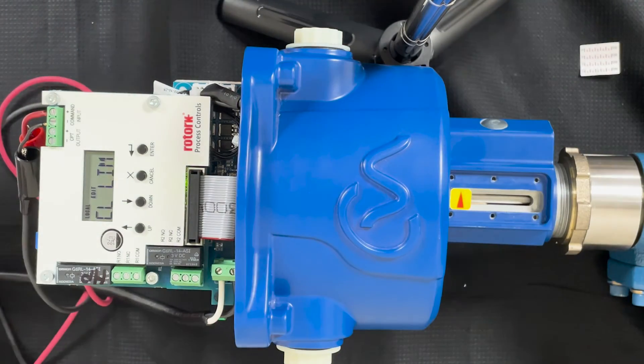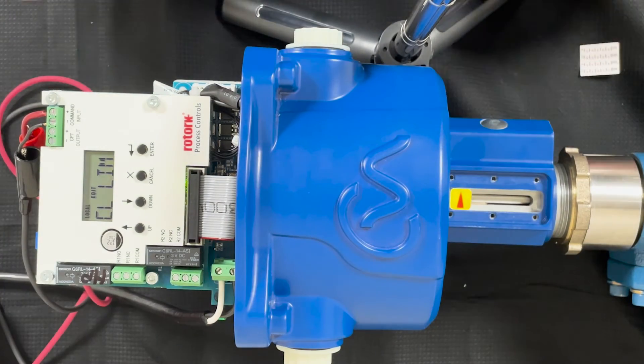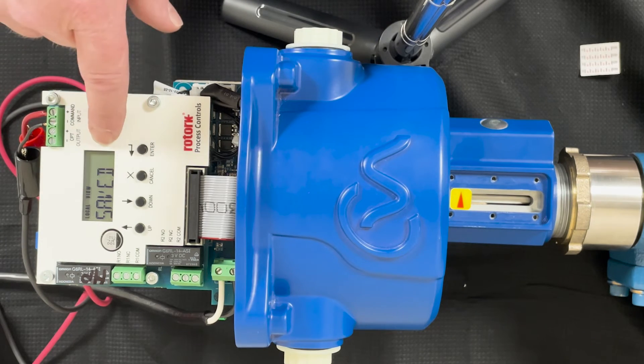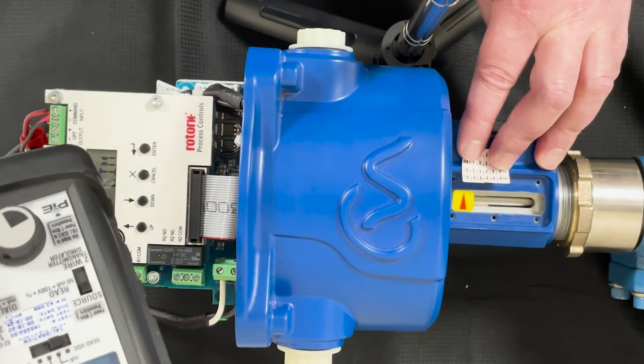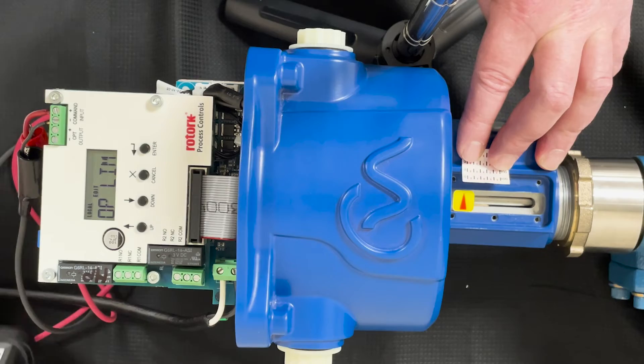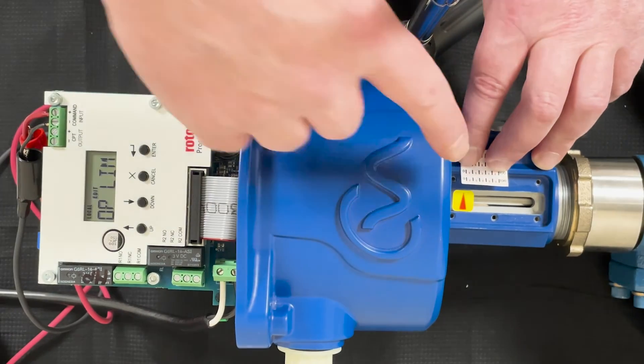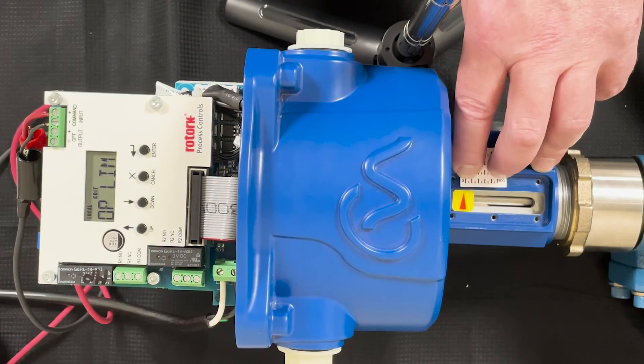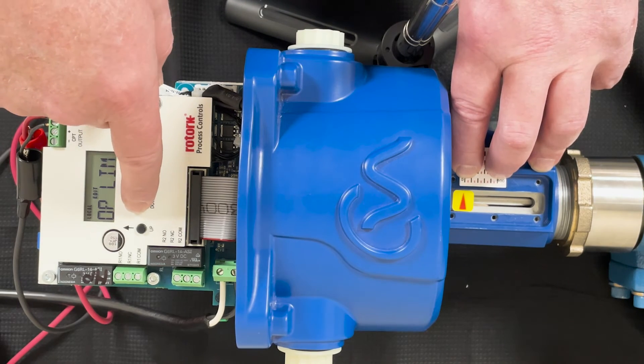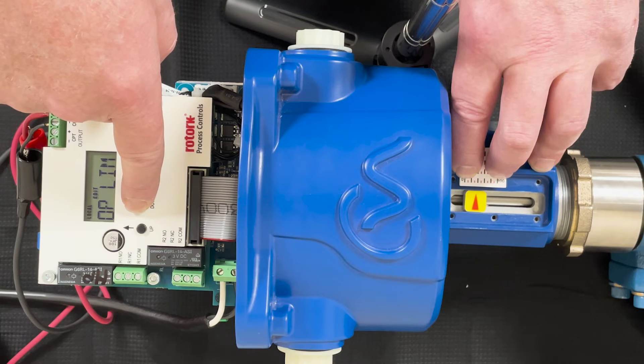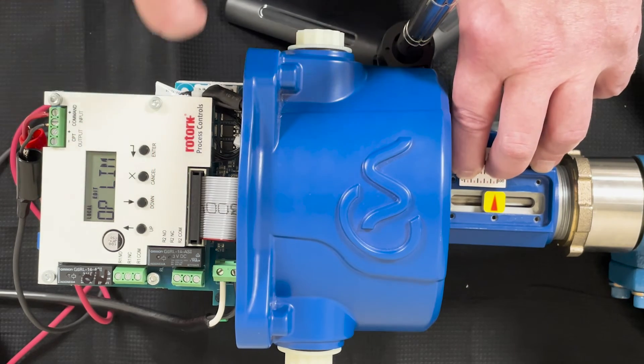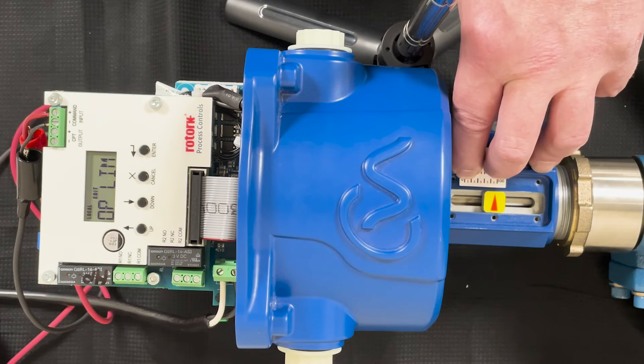We've got the 20 milliamp signal on the controller. Now we want to adjust over here to our 100 spot. We already did the zero, so we want to push our down button until we reach the 100 percent. Once you're at that 100 percent, we can save it.